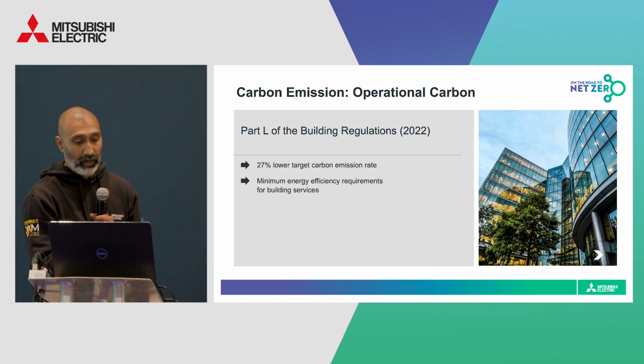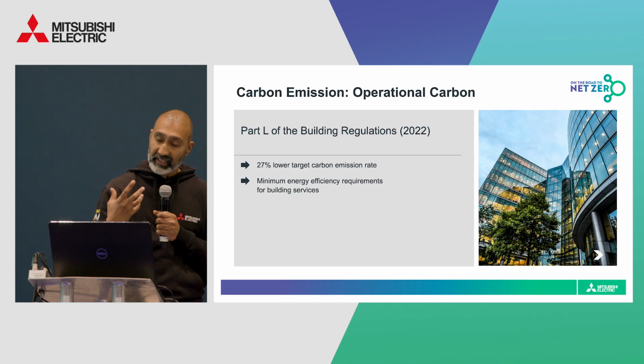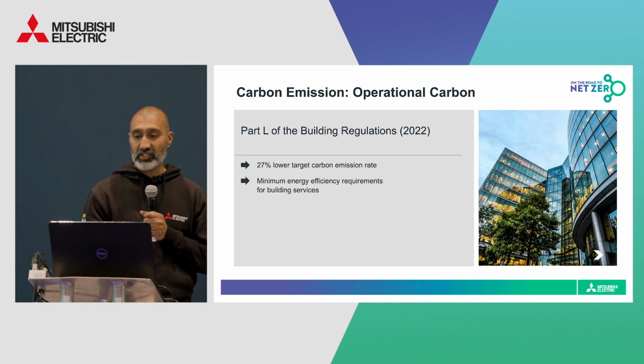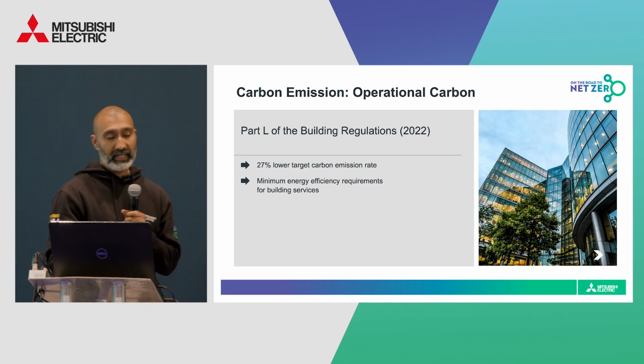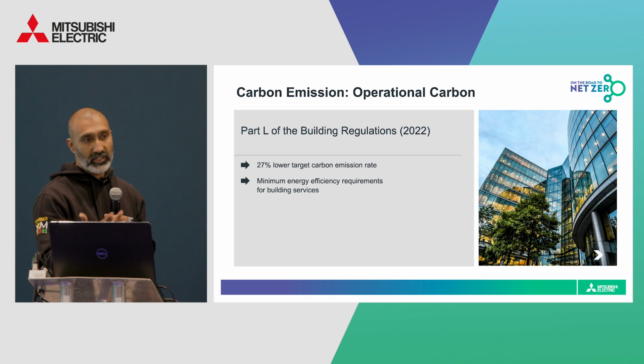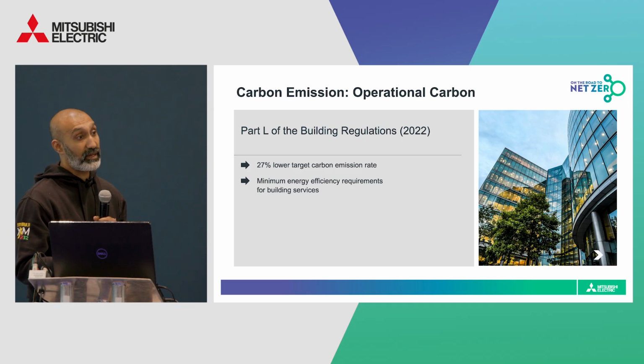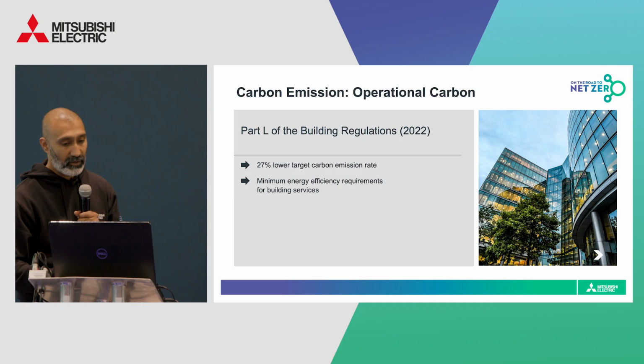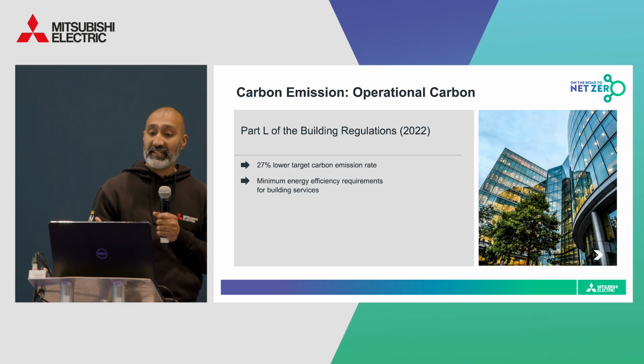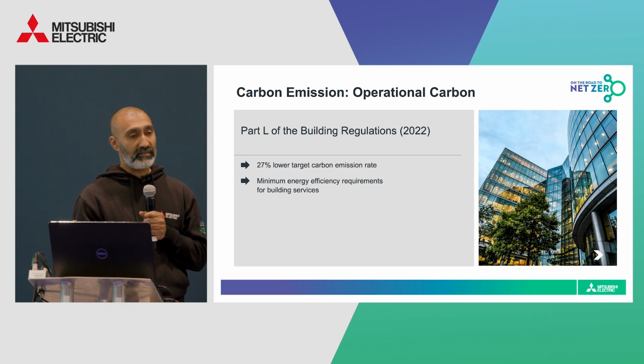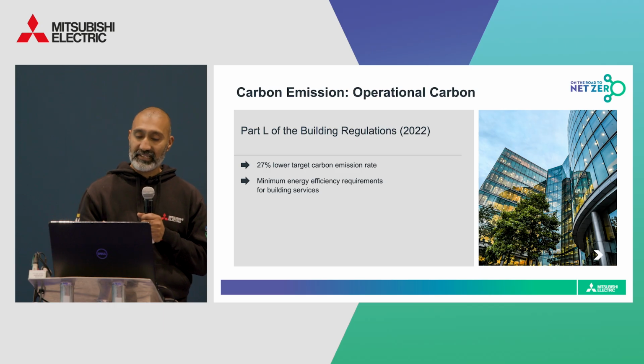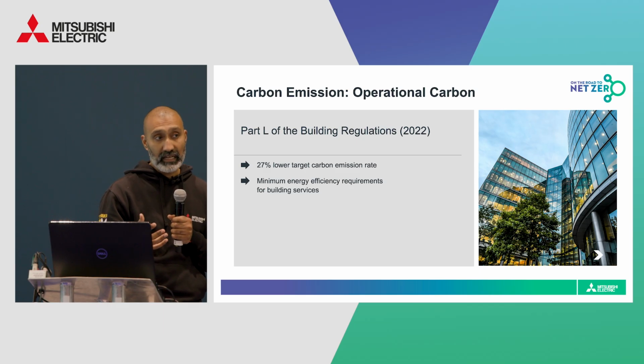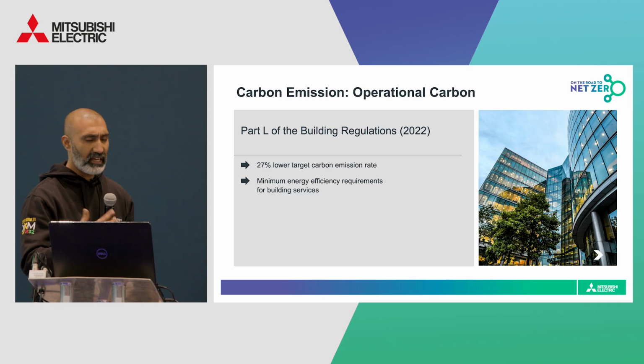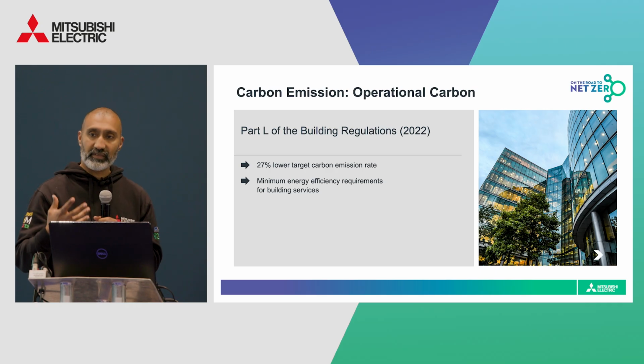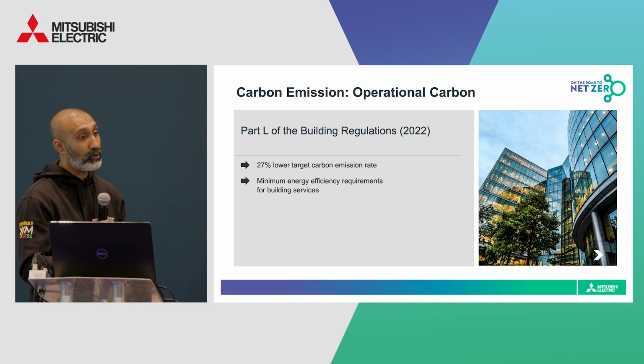So I've already mentioned Part L of the building regs, and this is a key regulation that impacts the specification of air conditioning systems that we put into buildings. In 2022, the regulation was updated, reducing the target emission rate for non-residential buildings by 27% compared to the previous Part L standards. And Part L also sets minimum efficiency requirements for building services equipment in both new and existing buildings, including heat pumps and comfort cooling systems. And these regulations all ensure that air conditioning systems are more energy efficient and help to reduce the carbon footprint of buildings.